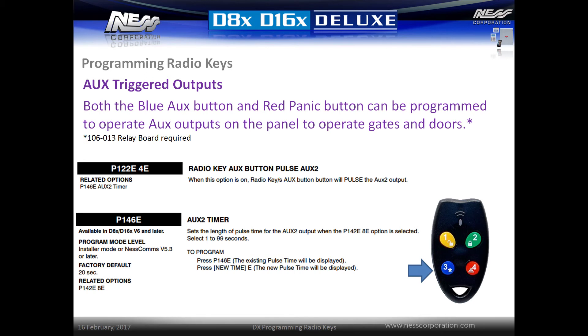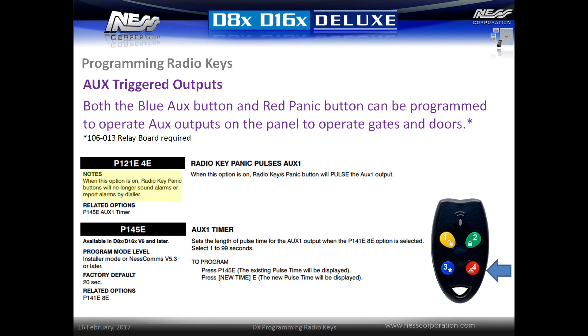Both the blue auxiliary button and red panic button can be programmed to operate auxiliary outputs on the panel to operate gates and doors. Note that the optional 106-013 relay board is required for dry contact outputs. To set the blue auxiliary button to pulse an output, enter location p122e and activate option 4e. To set the time for this output to pulse, enter option p146e and then enter the time in seconds — by default the pulse time is 20 seconds. To reprogram the red panic button as an auxiliary output button, enter location p121e and activate option 4e. To set the pulse time for auxiliary 1, enter location p145e and then enter a new time followed by E.